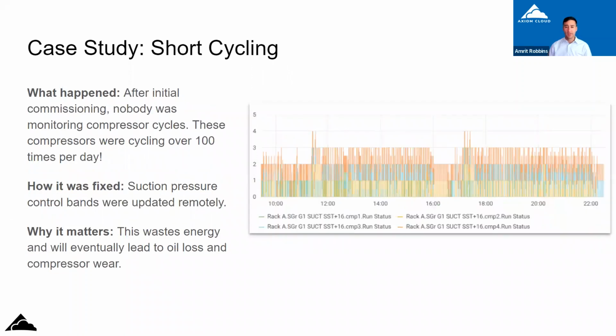So, here's another example where, just by looking at this data, you're able to see these various compressors, where each color represents one compressor in a suction group. You can see that these things are banging on and off all the time, many, many cycles per day, over 100 per day. And just like Trevor was talking about earlier, when a compressor short cycles, it starts by squirting out some of the oil inside of it, and then it takes a few minutes for that oil to get replenished. If you're short cycling, then you're just squirting out oil all the time. You're not giving it enough time to replenish. So ultimately, these compressors are running dry without an adequate amount of oil.